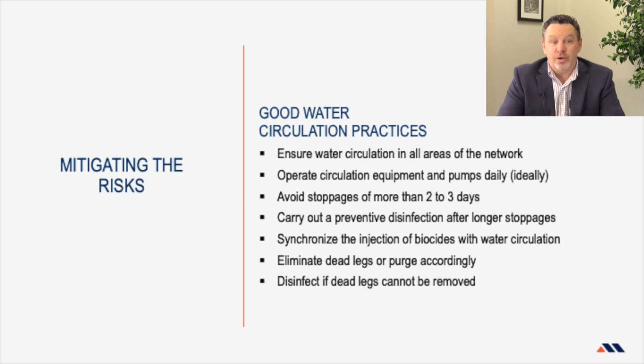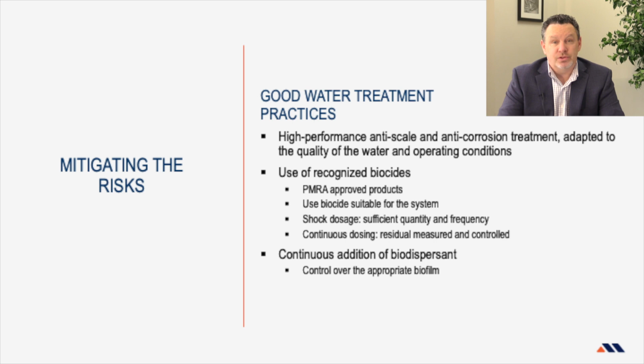Avoid stagnant conditions for more than 2-3 days at least. In other words, a long weekend is considered a long period for stagnation. So schedule circulation times. Every noon or every midnight or 10 o'clock, have the circulation pumps turned on for an hour and let that go through the system. Make sure that you avoid those stagnant conditions. And if for some reason you do need to have stagnant conditions for a long weekend, then when you have a startup, make sure you proceed with a preventative disinfection before startup. Those are really significant actions you can take to reduce the risk of people getting sick from Legionella. So it's literally impossible to eliminate all the risks.